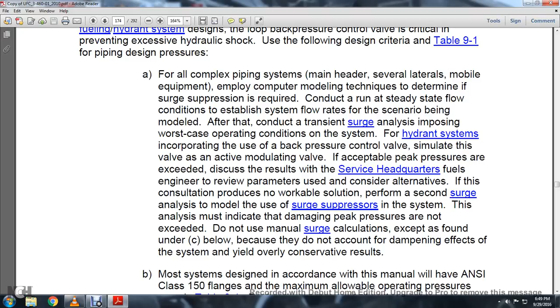Service headquarters fuels engineers review the parameters used and consider alternatives. If this consultation produces no workable solution, perform a second surge analysis of the model using a surge suppressor in the system. This analysis must indicate that damaging peak pressures are not exceeded. Do not use a manual surge calculation, except as allowed, because it does not account for the dampening effects of the system and yields overly conservative results.